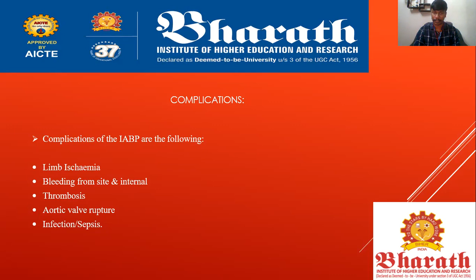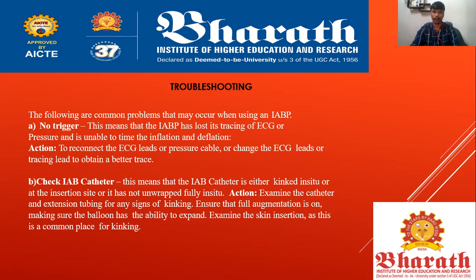And the IABP catheter will be examined, or checked at certain time periods, whether it is working properly, whether the balloon has the ability to expand and shrink when inflation and deflation is provided by the machine. So checking the IABP catheter is one of the troubleshooting steps. And rapid gas loss, some leakage can occur in the balloon due to rupture by the blood, or due to the working of the balloon against the blood flow. Some gas loss can occur.